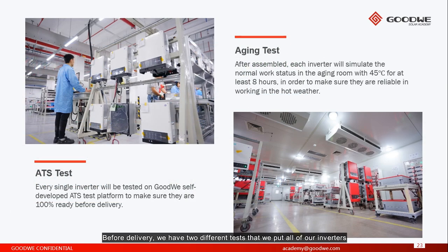Before delivery, we have two different tests that we put all of our inverters through — that's why we call it a 100% test. For example, the aging test: after assembly, each inverter will simulate normal working status in an aging room at 45 degrees for at least 8 hours, to ensure reliability in hot weather. And the ATS test, which is a GoodWe self-developed test — with the ATS test, we verify the grid code test, communication test, and all other functions are working normally.